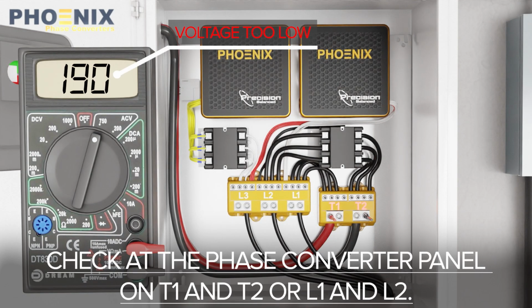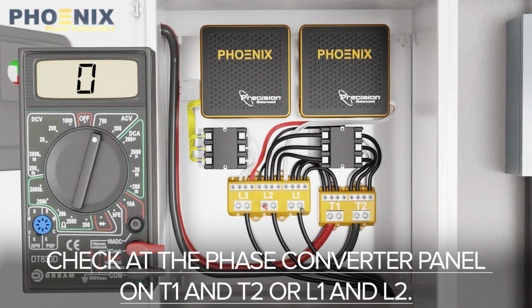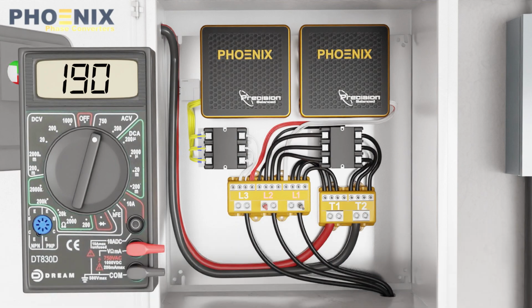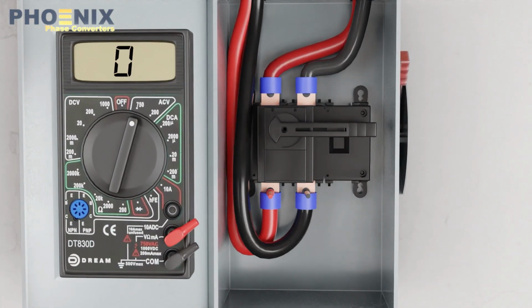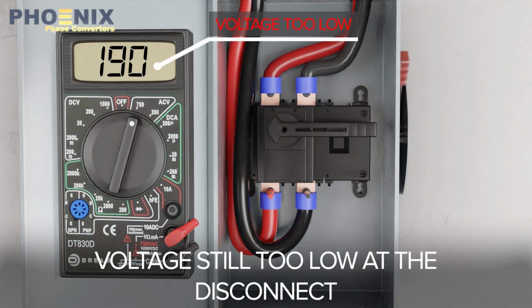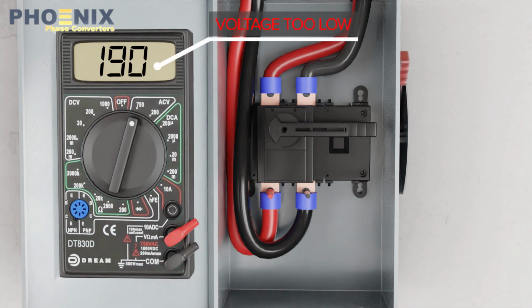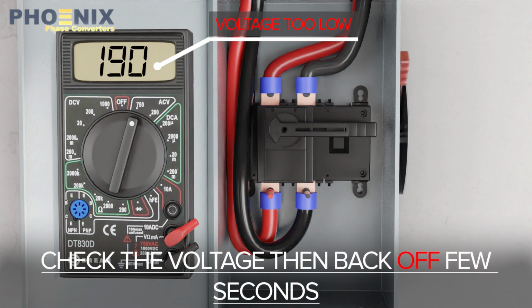Here is an example of your service is too weak. Check at the phase converter panel on T1 and T2 or L1 and L2. Voltage still too low at the disconnect. Remember, turn the phase converter on. Check the voltage, then back off few seconds.